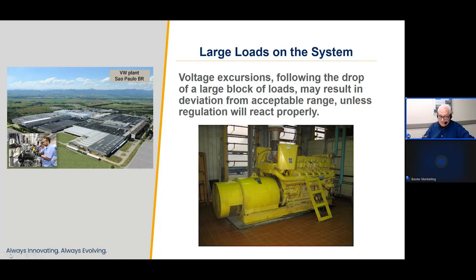My role in this project was to program the building's energy management system to strategically stage on controls to alleviate some of the stress on the emergency backup generators that had become frequently required in response to power outages. Before my arrival, the source of these power outages was not of interest to me, but that would change. The load staging strategy ran into trouble. The conductors to the loads had not been connected to the circuit breakers as had been assigned in the design of the power systems for the building. So the digital load control would have no benefit.